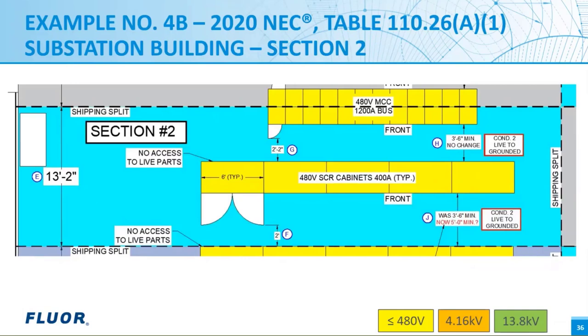On section two, we have a condition two where you have exposed live parts on one side and you have a grounded surface on the opposing side at bubble H. Since the motor control center door is only 16 inches and the opposing equipment here is a grounded surface on the backside of these SCR cabinets, then we've complied with a new sentence in the 2020 NEC already with a distance of 3 foot 6 inches from table 110.26(A)(1). As you can see, the dimensions here, 2 foot 2 near bubble G, meets the required 24 inch minimum clearance for the entrance into and out of the workspace with the doors of the MCC open.